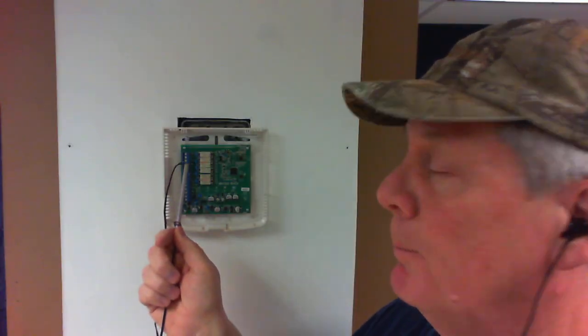Again, I get a lot of calls about the plenum sensor. What do I do with it? Where does it go? That's the bottom line. It is a fail-safe mechanism that's built into this thermostat model, both of them. It's there for safety feature to ensure that we can keep a minimum heat or cooling as needed. As long as your batteries are good in your thermostat and you have no communication loss issues, then this doesn't do anything. Like I said, doesn't do a thing at all. But it still needs to be installed. So that's the straight dope on this. So make sure you install it, connect it to P1 and P2, and you'll be golden at that point.